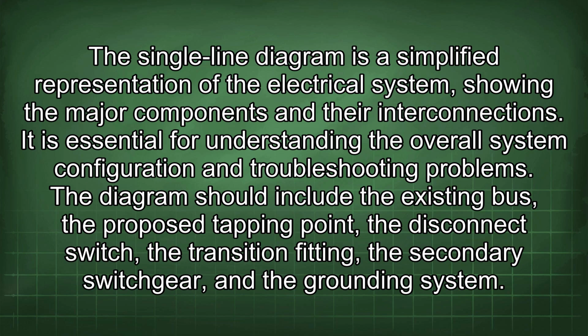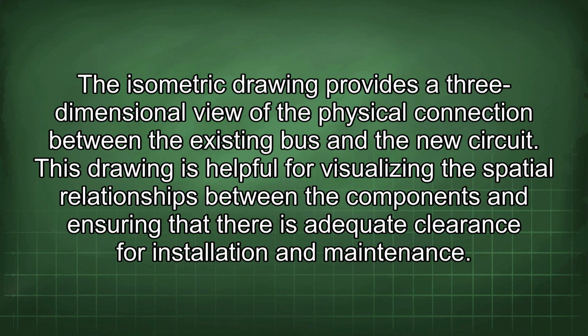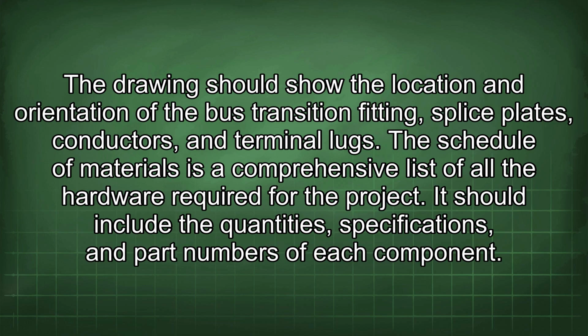and the grounding system. The isometric drawing provides a three-dimensional view of the physical connection between the existing bus and the new circuit. This drawing is helpful for visualizing the spatial relationships between the components and ensuring that there is adequate clearance for installation and maintenance. The drawing should show the location and orientation of the bus transition fitting, splice plates, conductors, and terminal lugs.